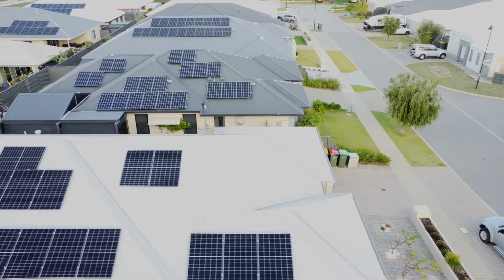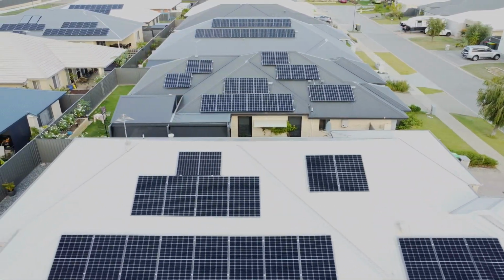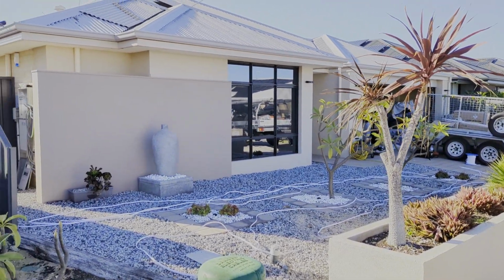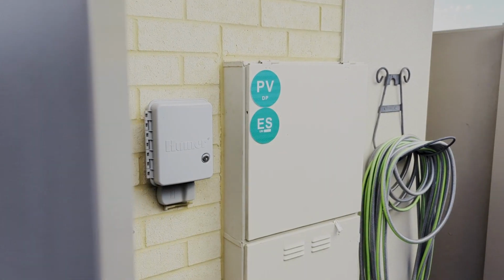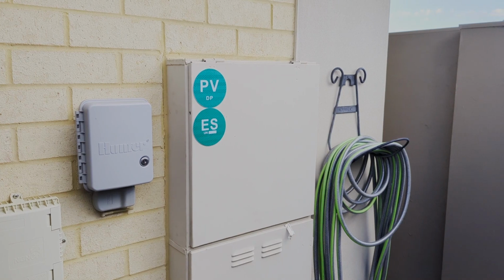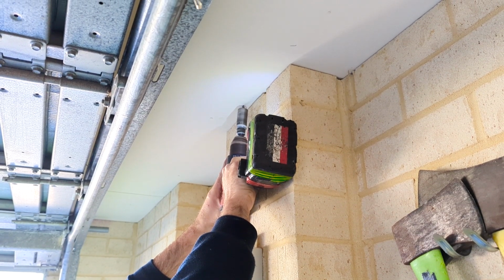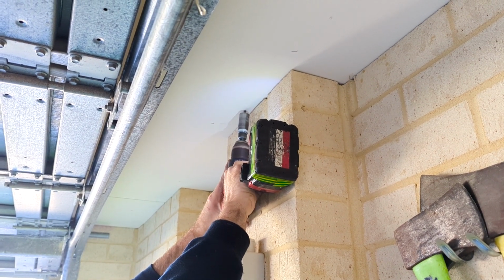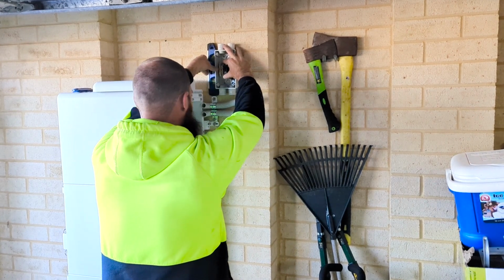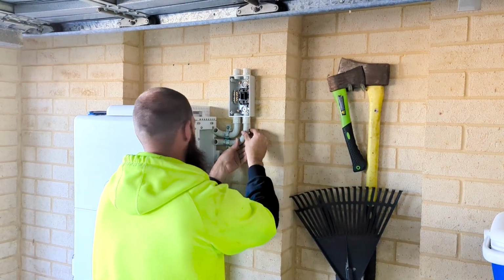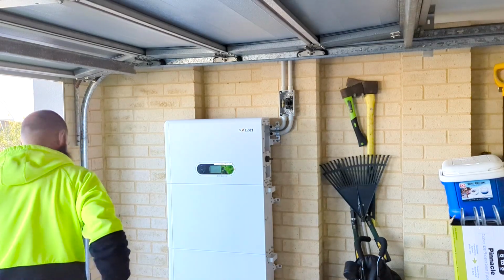With the inverter position decided, it is time to install the panels and run both the DC cabling bringing power down from the house and the AC cabling powering the home. Where possible, you should always run cabling through the wall, making the installation as clean as possible. If this is not possible, you can run conduit down behind or beside the PowerAll.